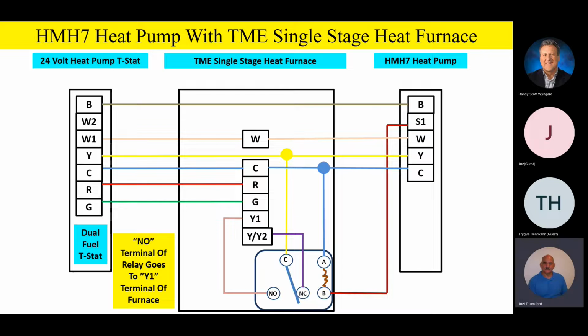So let me throw a little cog in there. Let me ask the group a question back. Let's say I had an S1 input and I was on reduced airflow. Let's say it was on Y1 airflow, reduced airflow, and then all of a sudden I get a heating call. Let's say reduced airflow is 800 CFM, and all of a sudden we get a W call, and the W call is 1400 CFM. What's the motor going to do? It's going to want to jump to the higher heating. Yeah, absolutely. Regardless of what S1 is doing, reduced airflow Y1 and Y2 or not, whatever airflow is higher that motor receives, it's going to jump to that airflow.